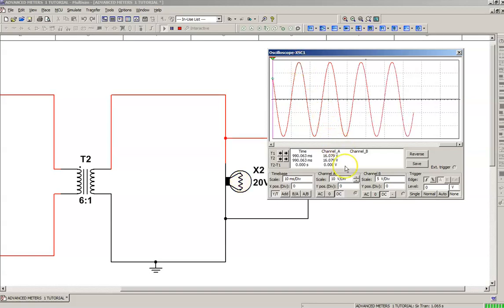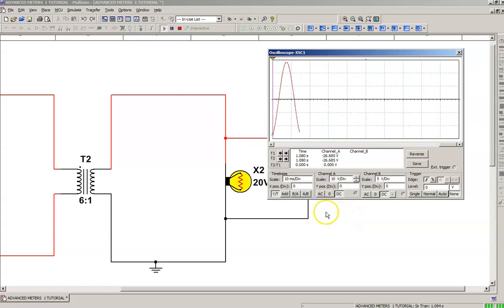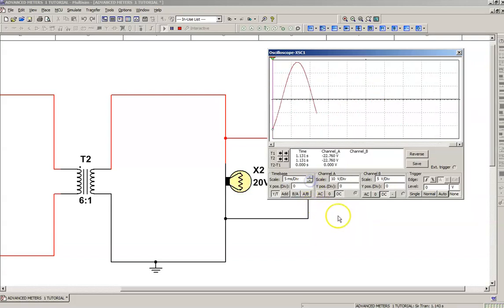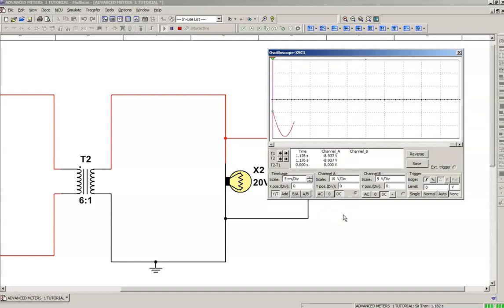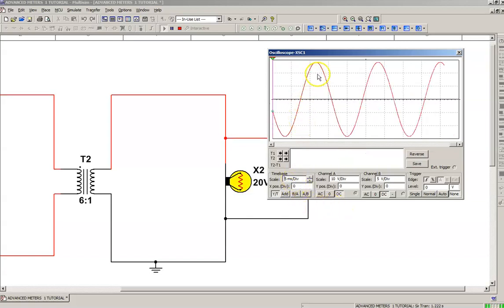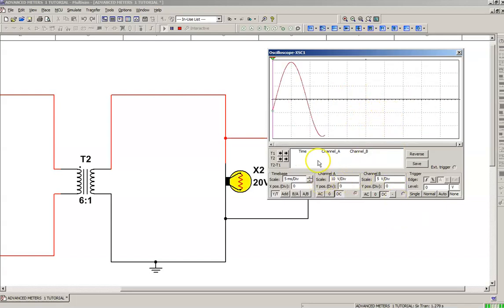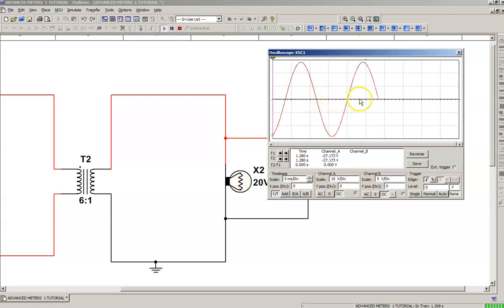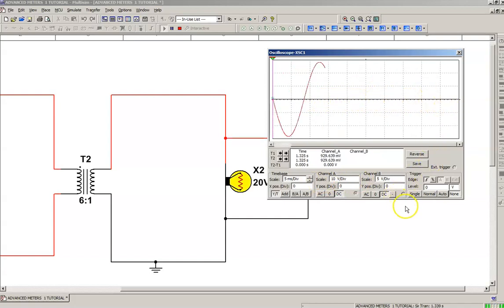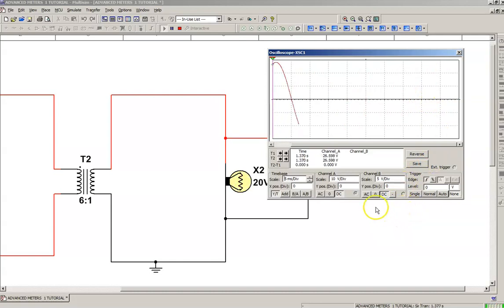Now, the time scale is set to 10 milliseconds. I'm going to change that. I'm going to set it to 5 milliseconds because it widens things out for me, and I can get a better understanding. This is the number that I use in the field because each one of these cycles takes about 16 or 17 milliseconds, about 16.67 milliseconds. So if I set it 5 milliseconds per division, I can get a couple of waveforms on there, and I can look for notches and distortions and so on.